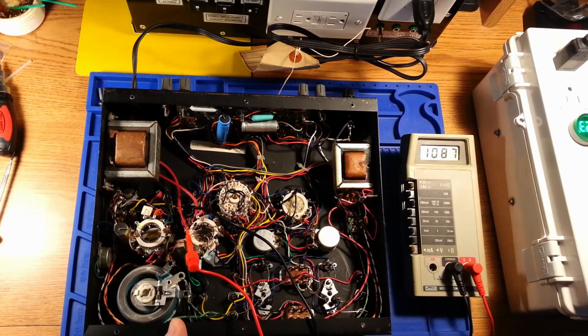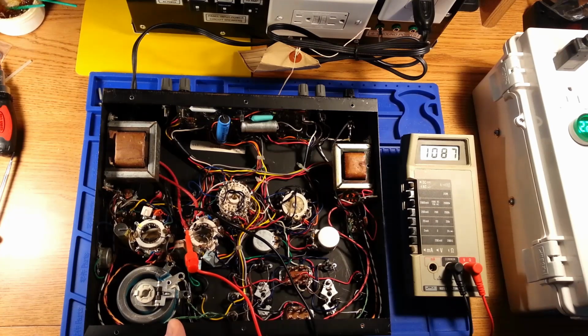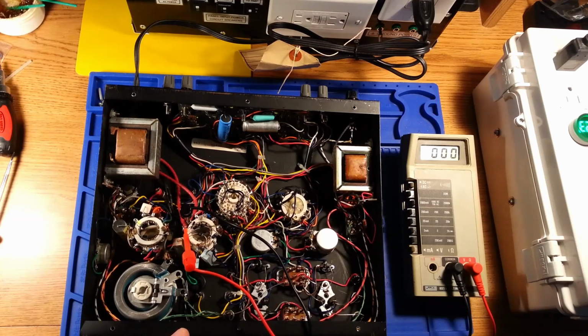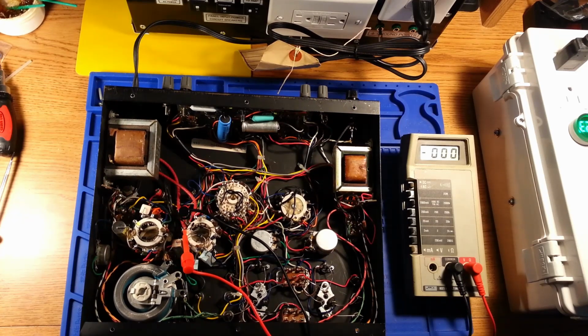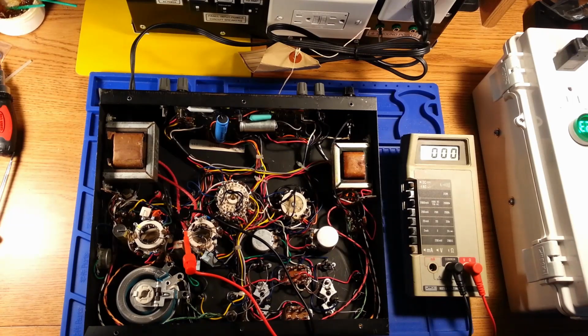And oh, we are indicating a 1000 volt AC voltage, even though this meter is only rated to 750 volts AC. It's indicating 1000 AC volts, which is really interesting. Going to go off. So the meter survived, and apparently the transformer's functioning as it's supposed to. There's no smoke or fumes or blown fuses or anything. So going forward, I'm going to think that it's a successful unit to work on.